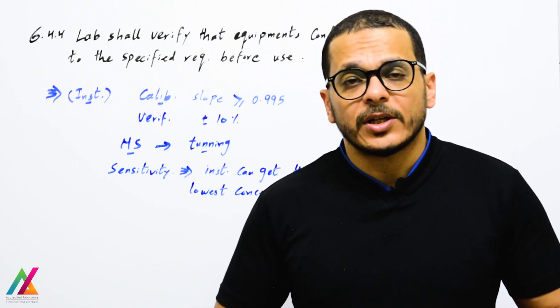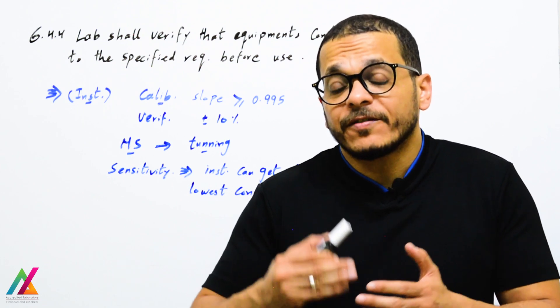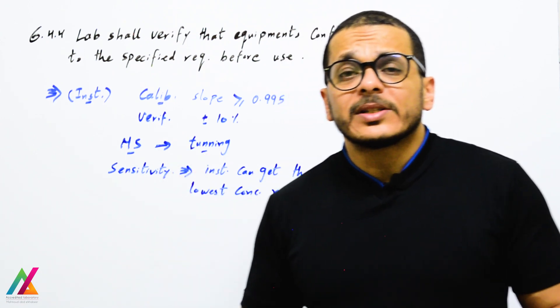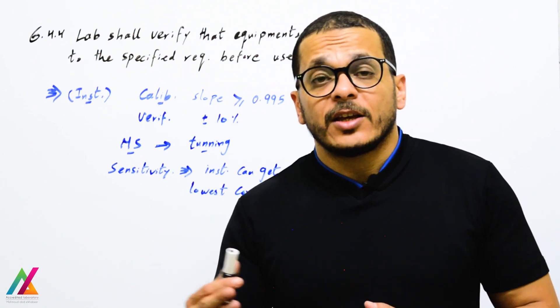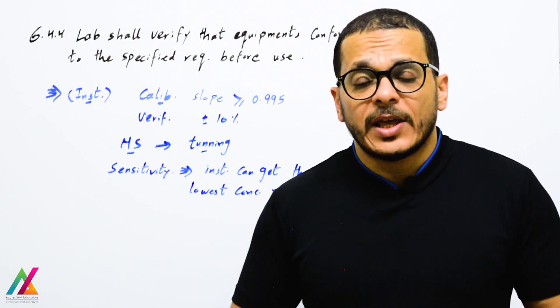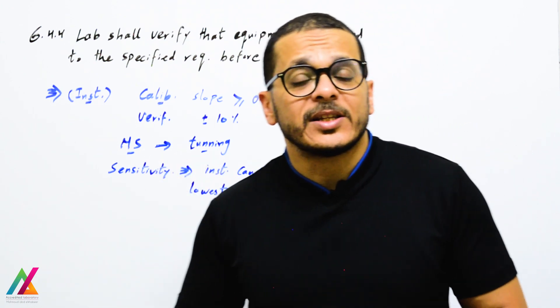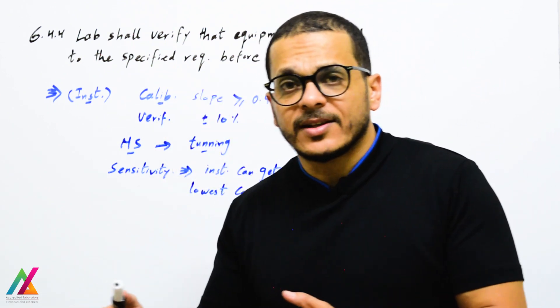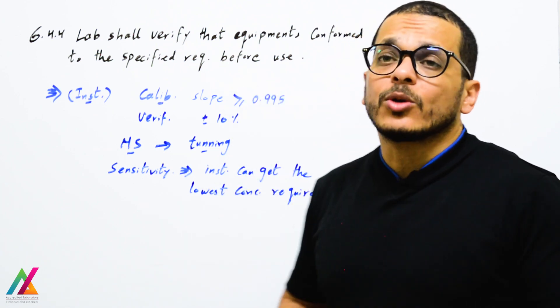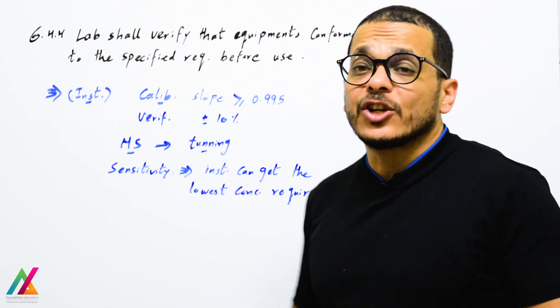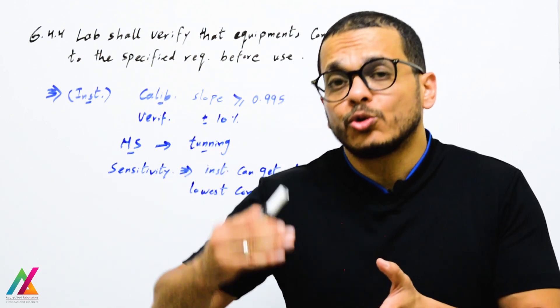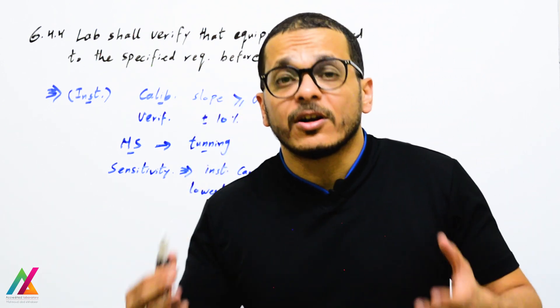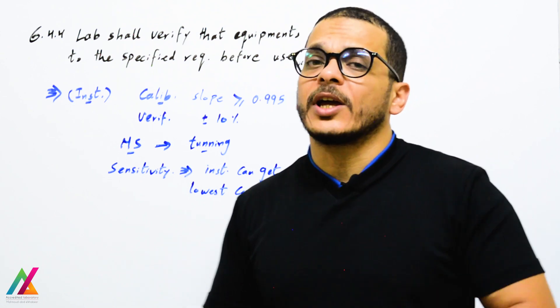The lab shall verify that equipment conforms to specified requirements before use, to ensure valid results. For instruments, after setup you shall perform calibration, verification, and sensitivity checks. For instruments such as GC-MS or LC-MS, tuning the mass spectrometer is also required. Calibration shall achieve a slope ≥ 0.995 to be accepted. A verification standard — ideally from a different supplier than the calibration standard — shall also be run.